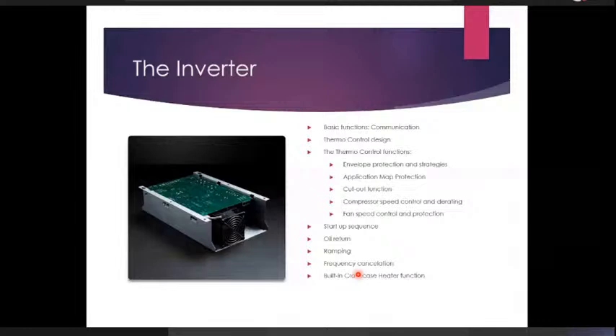But the whole purpose of putting it up here is that this chart will determine whether or not it is safe to operate the compressor at a certain RPM. So this has to be built into the logic of the embedded control.